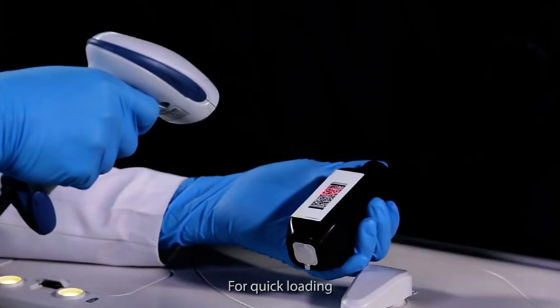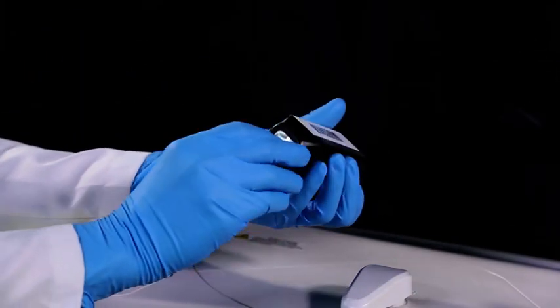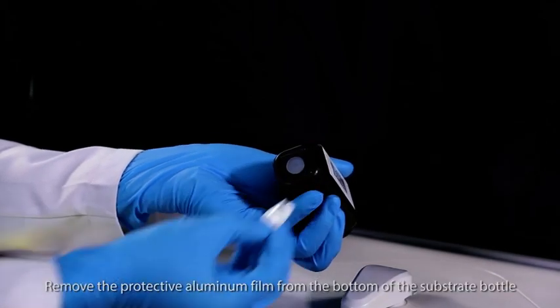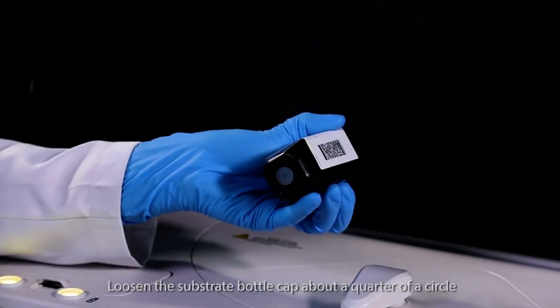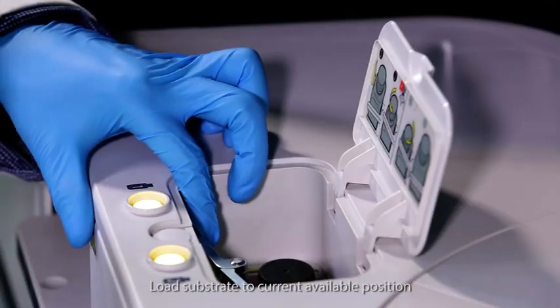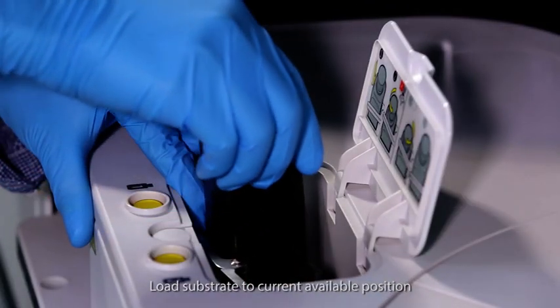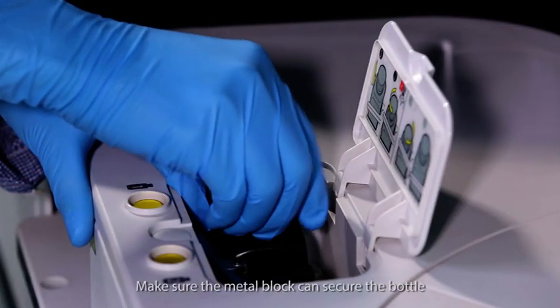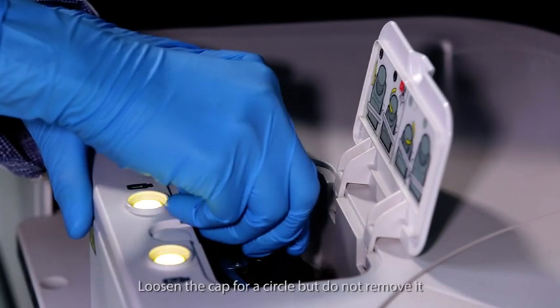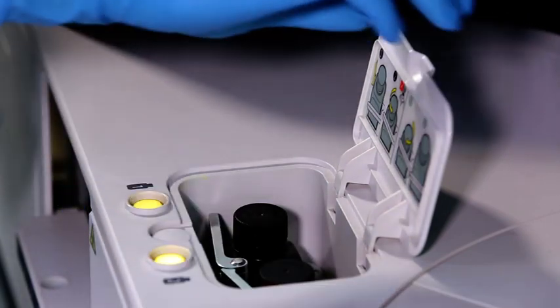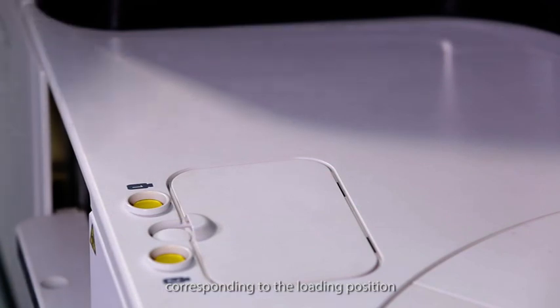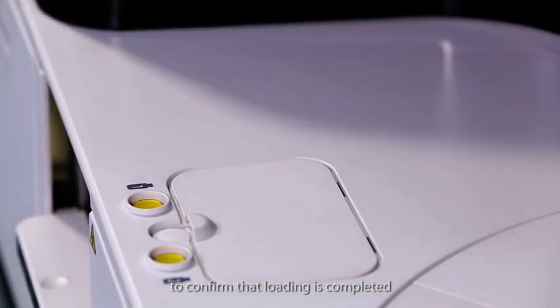For quick loading, scan barcode on the substrate bottle. Remove the protective aluminum film from the bottom of the substrate bottle. Loosen the substrate bottle cap about a quarter of a circle. Load substrate to current available position. Make sure the metal block can secure the bottle. Loosen the cap for a circle, but do not remove it. Press the indication light corresponding to the loading position to confirm that loading is completed.